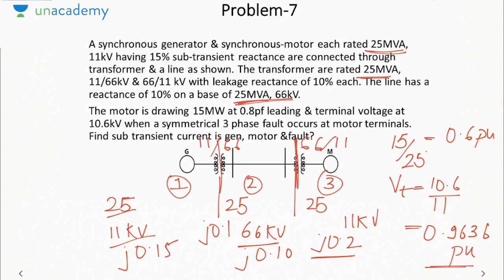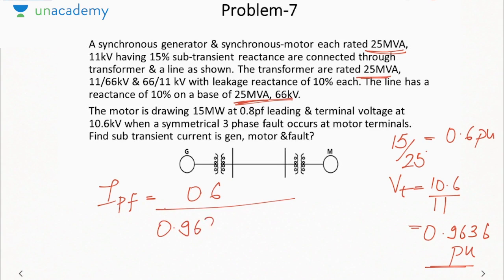Okay, this will be the terminal voltage. To calculate the current before the occurrence of fault, what we will do? We will divide the power by V cos phi. That is, I pre-fault will be 0.6 divided by 0.9636 into power factor. Power factor is 0.8 leading. So this current will come out to be 0.7783. Since it is leading, the angle will be 36.9 degree PU.